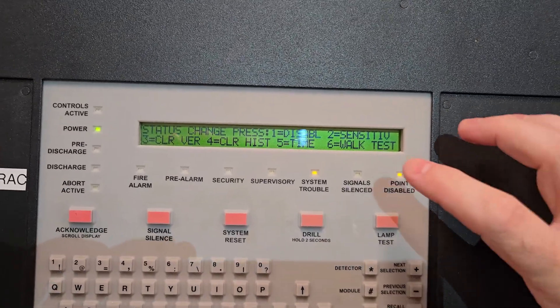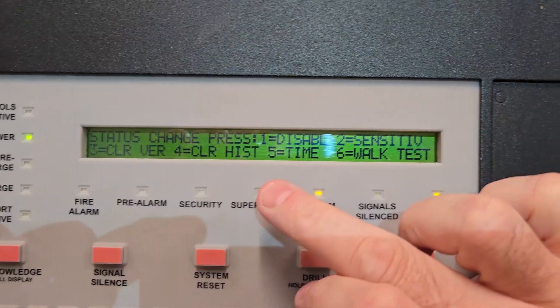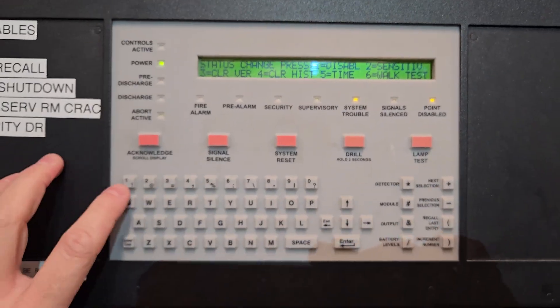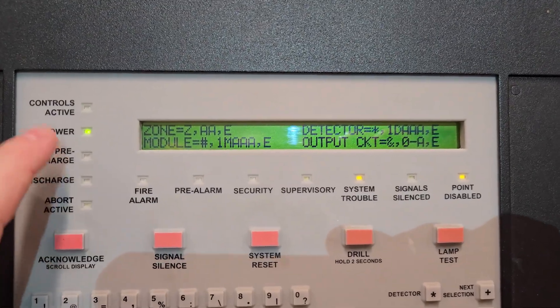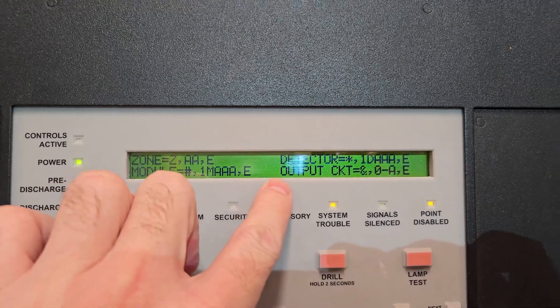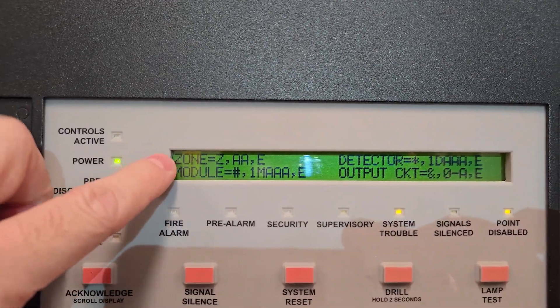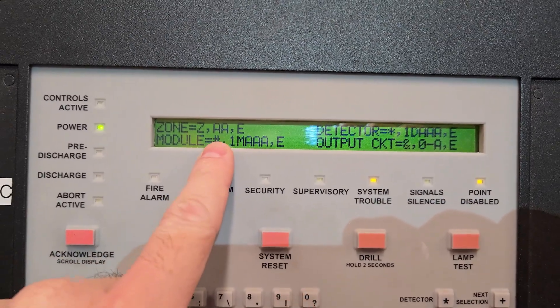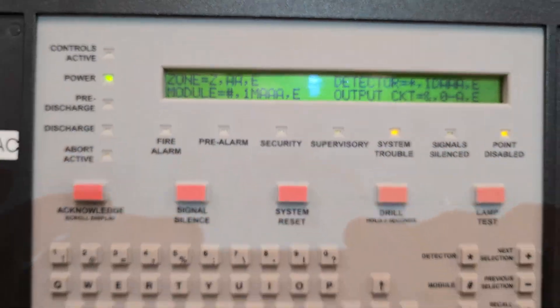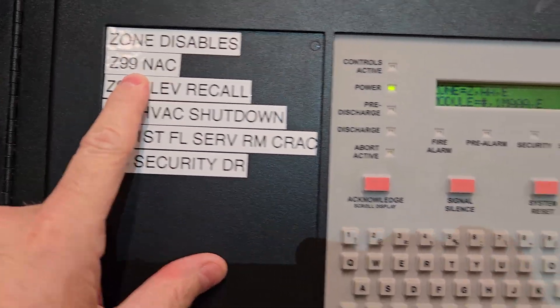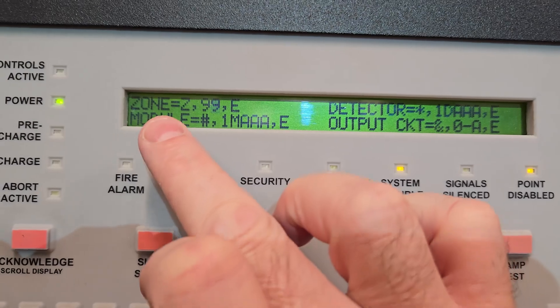Now I'm in the menu. I acknowledge the trouble to silence it. I have the same options: disable, sensitivity, history, time, and walk test. Number one equals disable, so I hit number one. It gives me the option to choose: zone, module, detector, or output. I'm going to hit Z for zone. Now it's flashing with the two A's ready for input. I enter 99 because that's my NAC zone. Zone 99 is now showing with the E for enter, so I hit Enter.